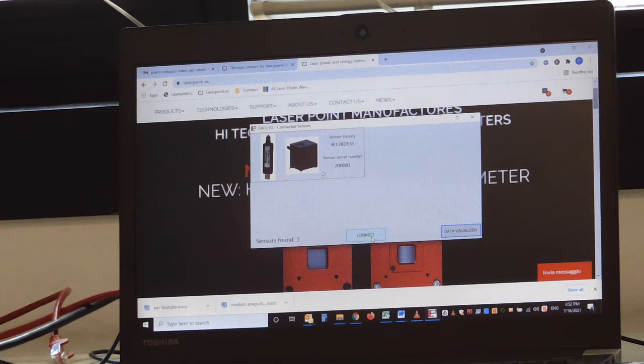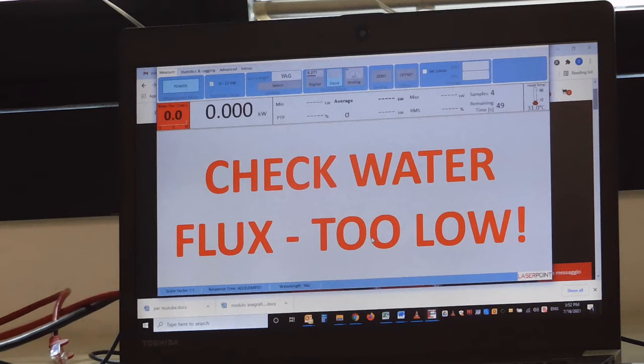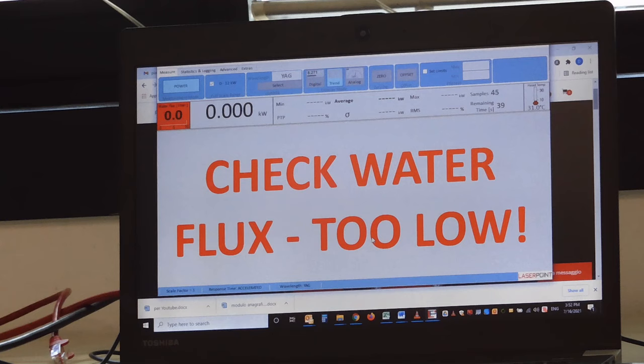Now, the software will read the EPROM memory inside the device. And I get the first warning coming from the system telling us that the water flux is too low. So I open the cooling water.